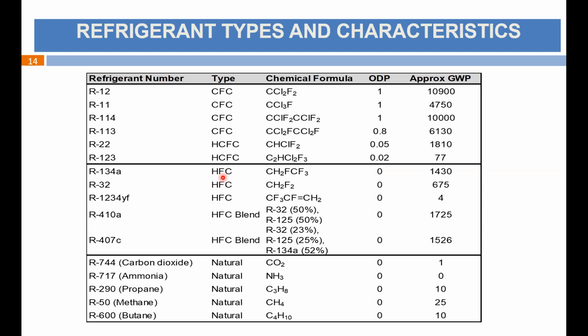Now come to the next generation refrigerants, which we are using now, mostly HFC and blends of HFCs. Here, although the ODP is 0, it has got high GWP. R410A has as high as 1725 GWP, global warming potential. R32 has a GWP value of 675. R134 is 1430. So as per the Kigali protocol, these refrigerants are also required to be phased down. But on the other side, natural refrigerants like CO2, ammonia, propane, methane, butane have very good thermodynamic properties. ODP is 0, and the GWP value is also very low.